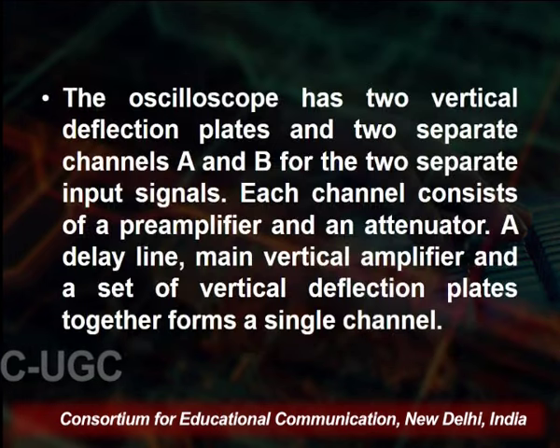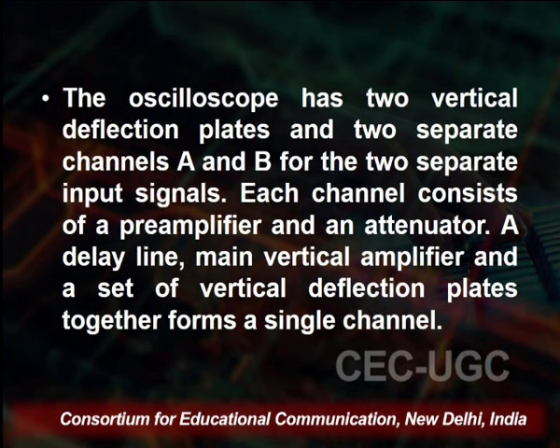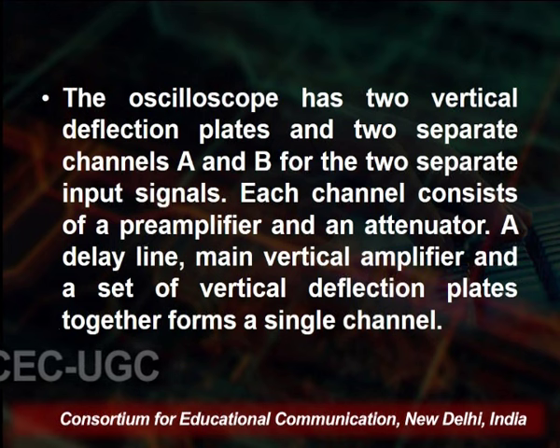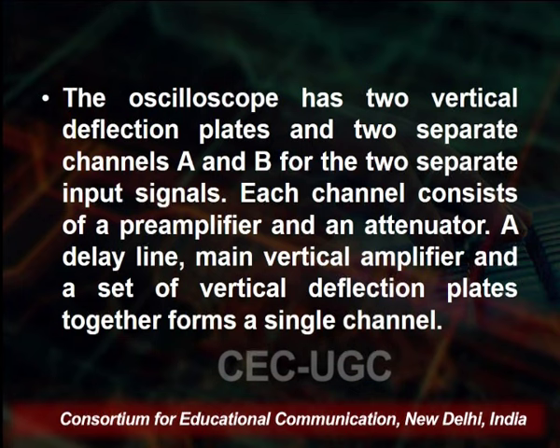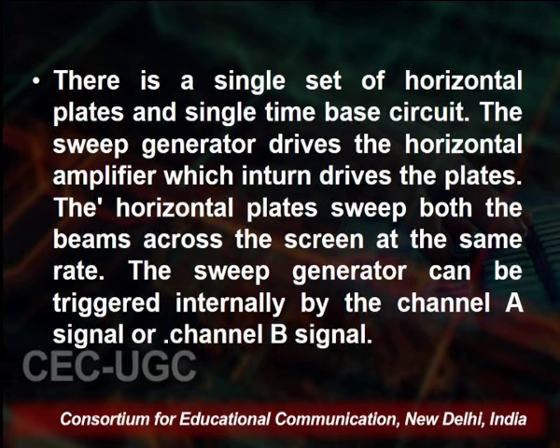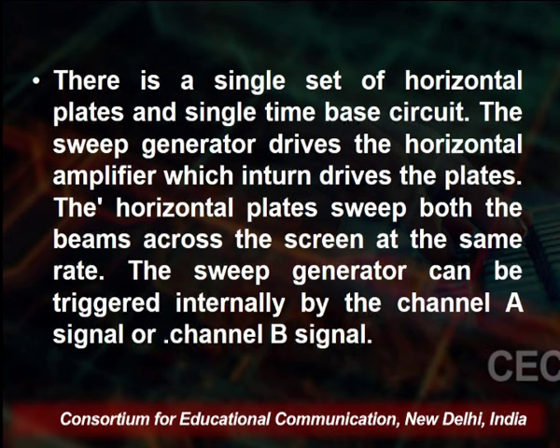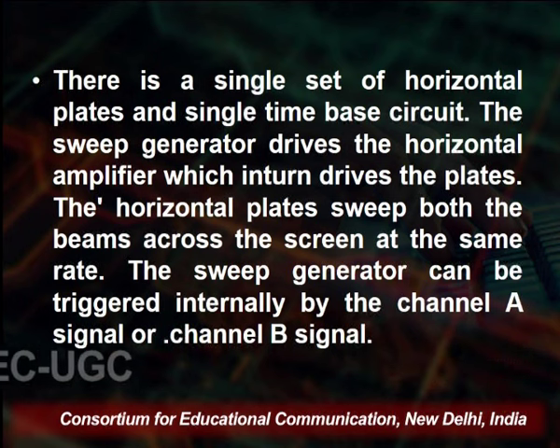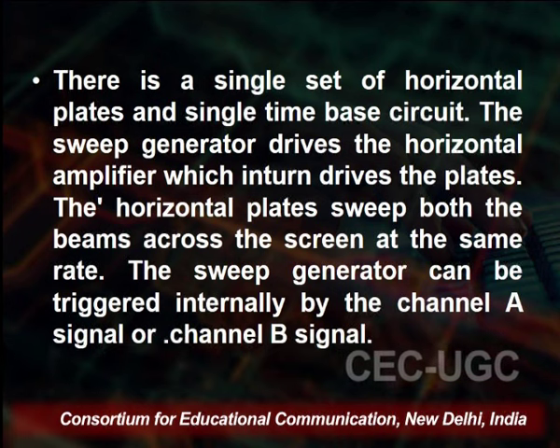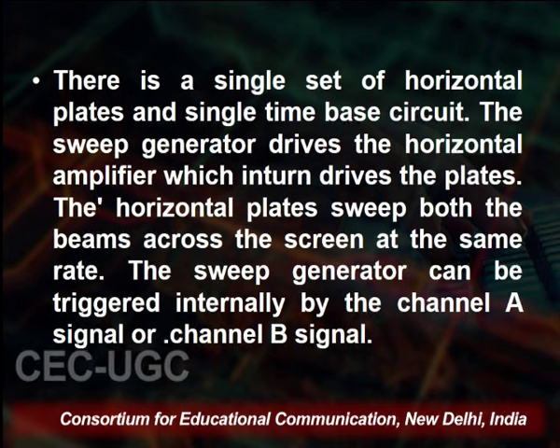Each channel consists of a pre-amplifier and an attenuator. A delay line, main vertical amplifier, and a set of vertical deflection plates together form a single channel. There is a single set of horizontal plates and a single time base circuit. The sweep generator drives the horizontal amplifier which in turn drives the horizontal plates. The horizontal plates sweep both beams across the screen at the same time.